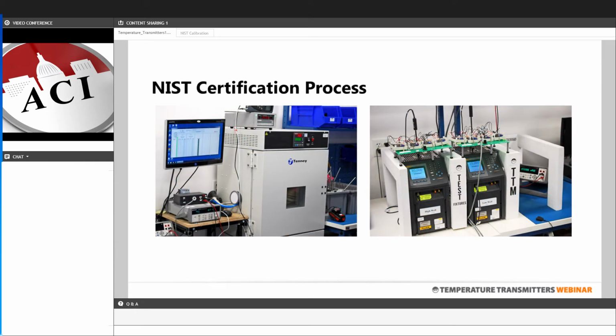When we do the NIST certification process, we take the extra step of pairing a specific sensor to a specific transmitter, testing it in an NIST traceable chamber, and then documenting the results of that testing and providing that documentation with each individual sensor.